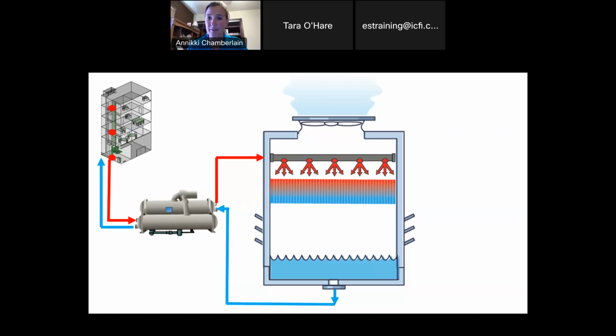Well, as we're evaporating water, only pure water evaporates, right? So we're increasing the minerals that are in the water. They're getting left behind, so we're increasing that mineral concentration. The more we evaporate, the higher that mineral concentration gets. Eventually, it could get so high that we get scale forming. These minerals in the water are always trying to reach equilibrium. So if we let the mineral concentration get too high, it's going to harden on our machine, and inside of our chiller, effectively putting a rock, a piece of limestone, on a surface we want to transfer heat. That wouldn't be very effective.